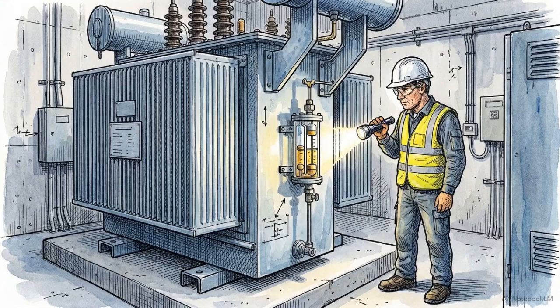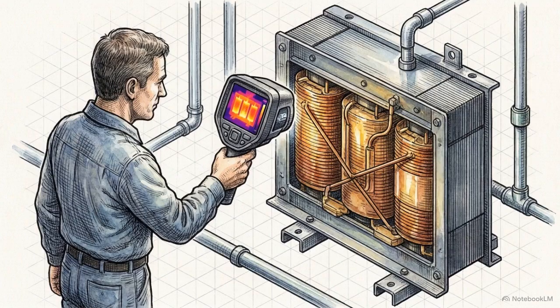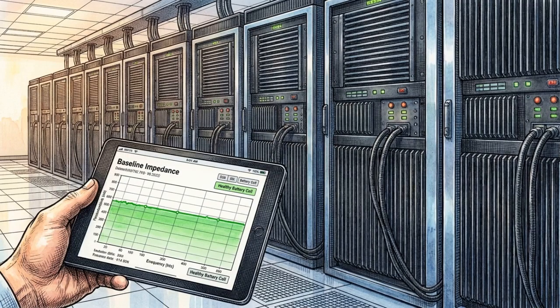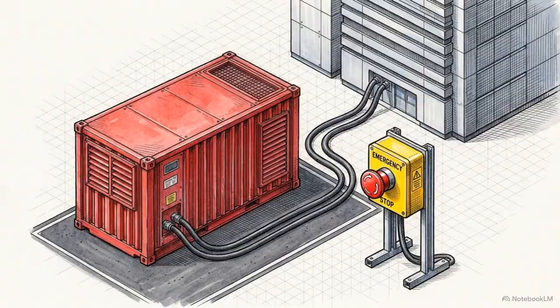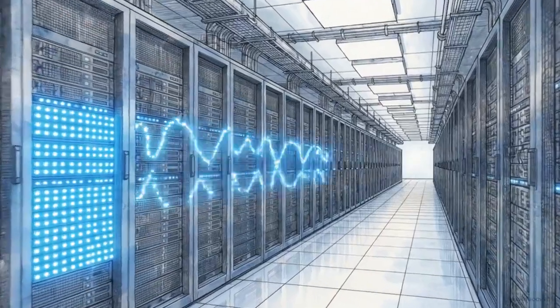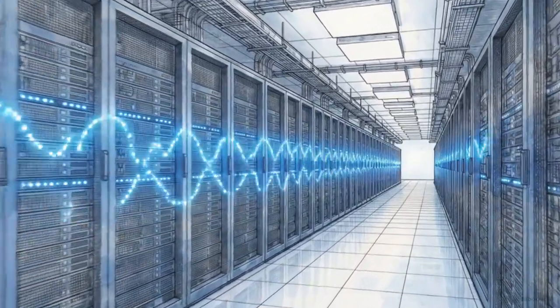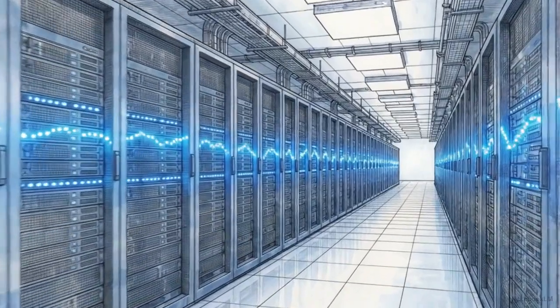Major electrical packages require specific evidence based on their design. Oil-filled transformers must pass containment and Buchholz relay tests, while dry-type units require resin inspection and thermal stability proof. Battery systems cannot pass commissioning without capturing raw baseline data. This provides operations with the necessary reference point to track cell degradation over time. Load bank testing is considered invalid if the temporary heat rejection path and emergency stops are not commissioned in tandem with the electrical draw. An electrical path is only secure when the telemetry, baseline data, and failsafes are proven to operate simultaneously with the power delivery.